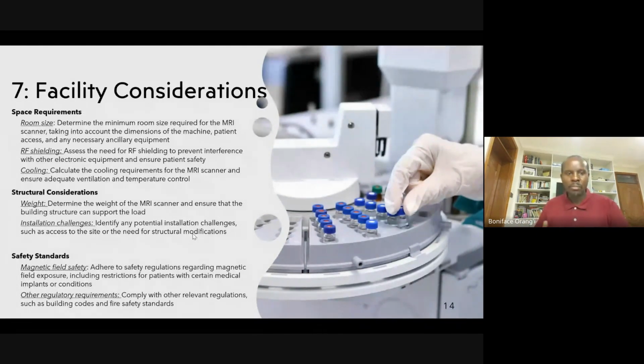So you'll have to deploy chillers. You'll have to make sure that the MRI comes with compressors and all that. But the hospital will be providing the chiller that provides the chilled water that goes to cool the helium. And the helium is what actually reduces the temperature of the metal to zero resistance, sorry, which is the basis of superconductivity.